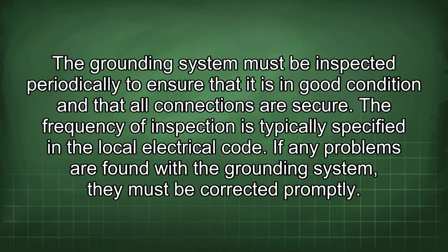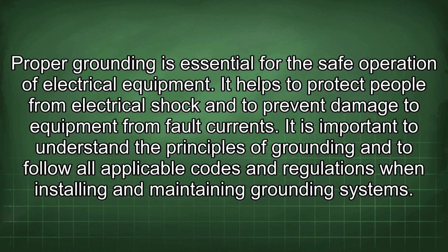The grounding system must be inspected periodically to ensure that it is in good condition and that all connections are secure. The frequency of inspection is typically specified in the local electrical code. If any problems are found with the grounding system, they must be corrected promptly. Proper grounding is essential for the safe operation of electrical equipment. It helps to protect people from electrical shock and to prevent damage to equipment from fault currents.